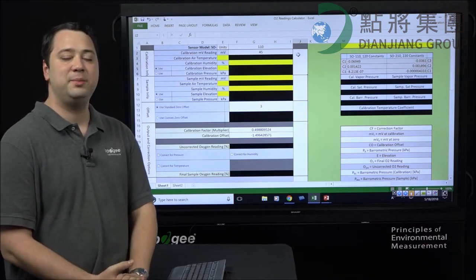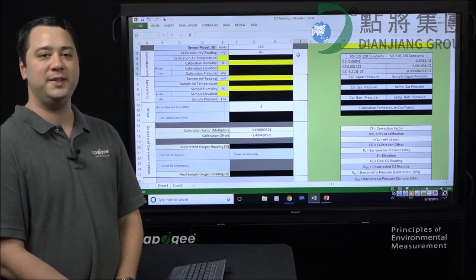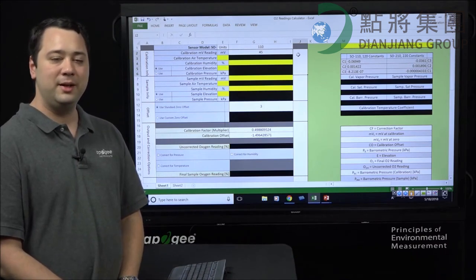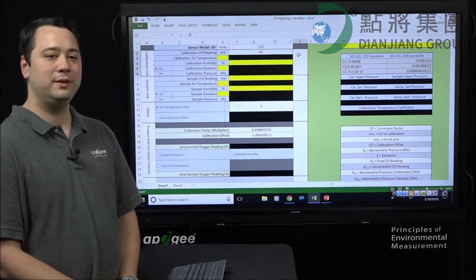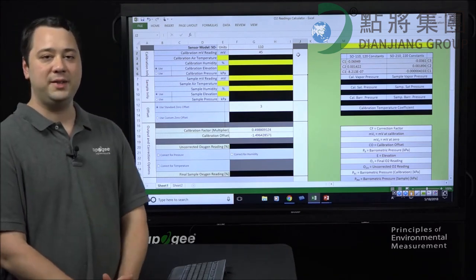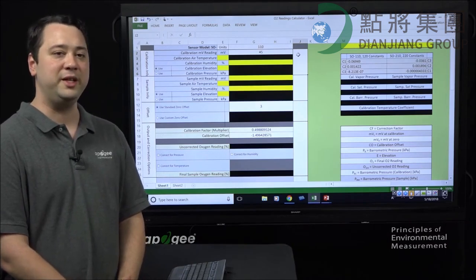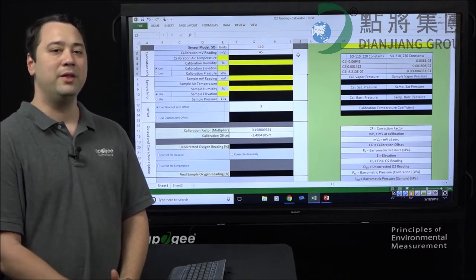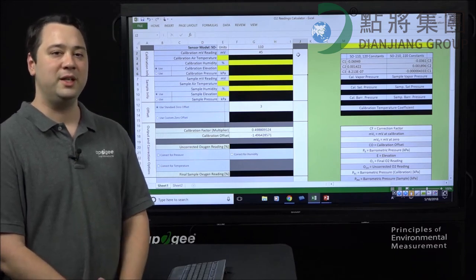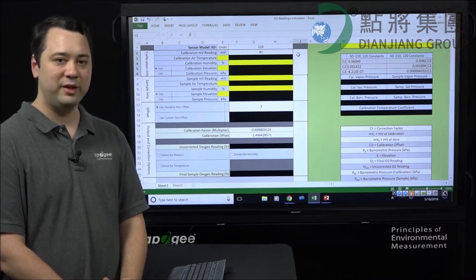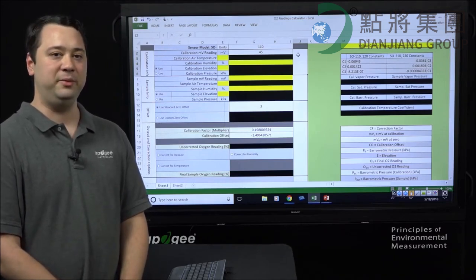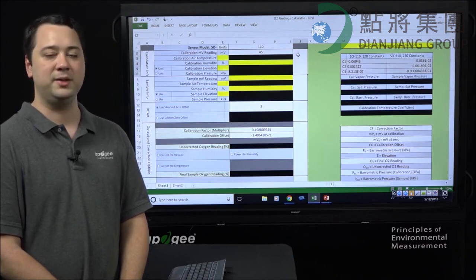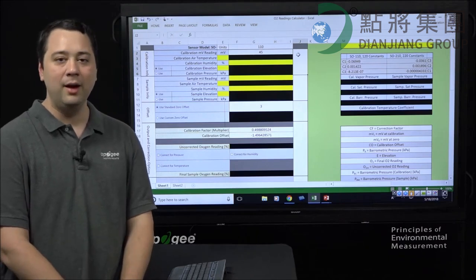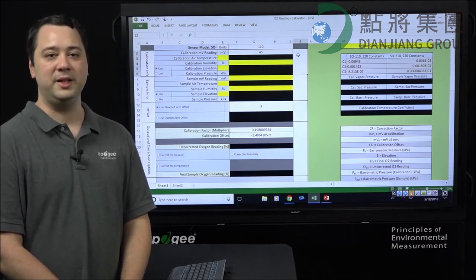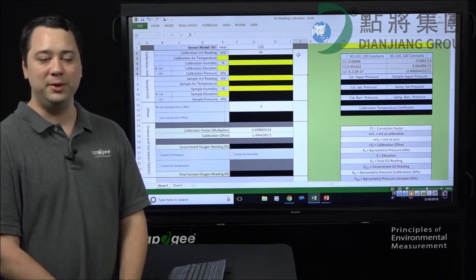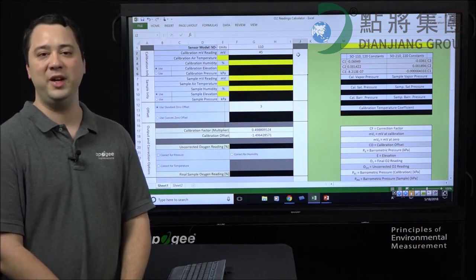An additional thing that this spreadsheet does is it allows you to correct for changes in environmental conditions. Now this is important because the oxygen sensor outputs a millivolt signal based on absolute oxygen concentrations, which we convert into relative oxygen concentrations. The reason we don't just use absolute concentrations is because many environmental factors affect them. For example, if you're at sea level, the relative oxygen concentration in open air is going to be roughly 20.95%. On top of Mount Everest, it's also going to be 20.95%, but the absolute concentration of oxygen between these two environments will be very different.